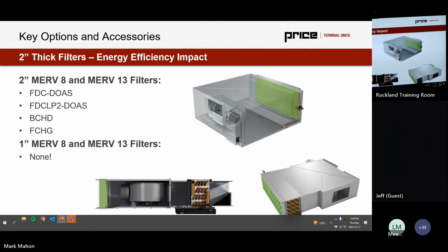Yeah, absolutely correct. So for everyone online, Ken, my favorite man in the audience today, because he's got answers for everything, said lower initial pressure drop for the same level of filtration, and that's absolutely correct. These filters are typically pleated, right? So HEPAs are pleated, MERV 13s are pleated, MERV 8s are pleated, and the thicker they get, the larger the effective surface area is, which actually means we're going to get lower pressure drop even though the filter is visibly larger. It looks like it should provide more, but it provides less.